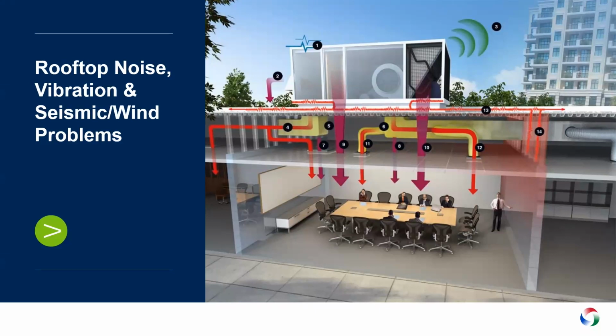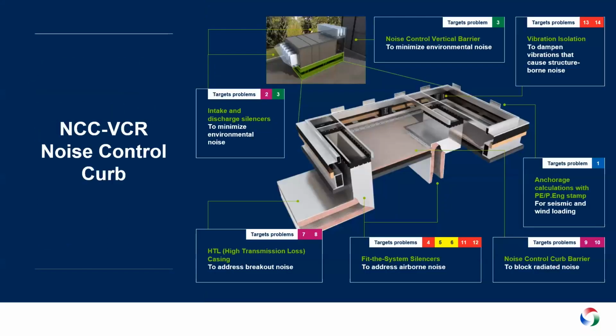To control all of these noise paths, we have a solution we call an integrated noise control curb solution, which is basically a package of vibration isolation curb, acoustical barrier, and supply and return silencer. Vibro-Acoustics will provide an end result guarantee solution, and we do provide PE stamp calculations for pressure drop, acoustical performance, and even wind and seismic rating if required. This is a really nice solution when we are concerned about noise traveling from the equipment right below.